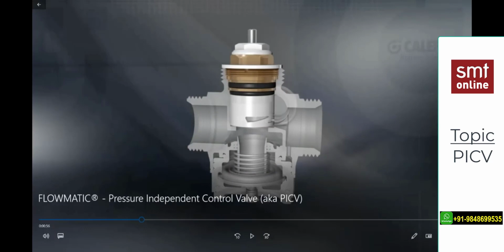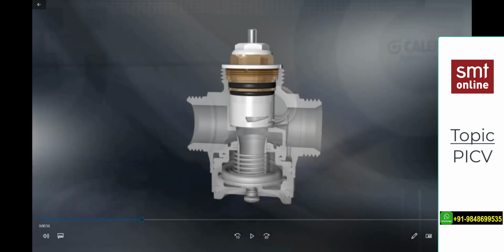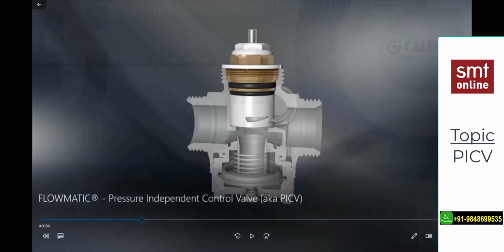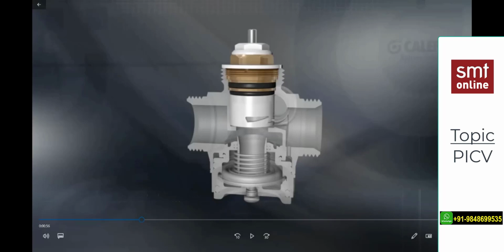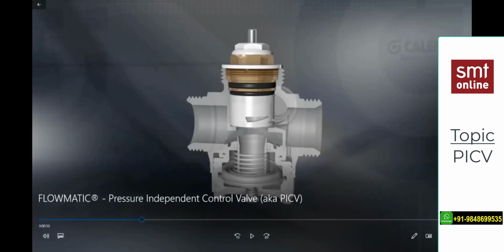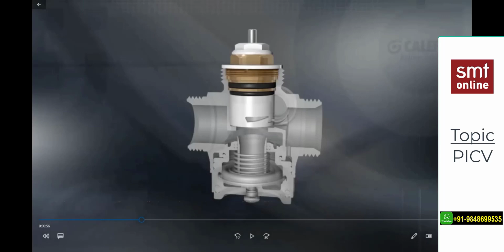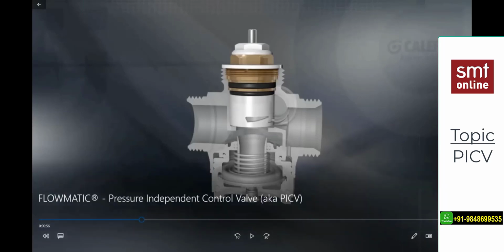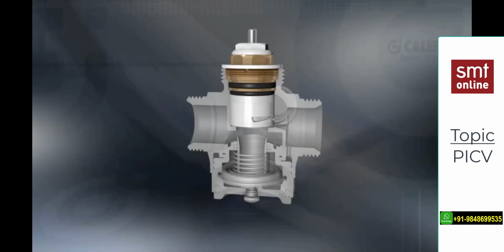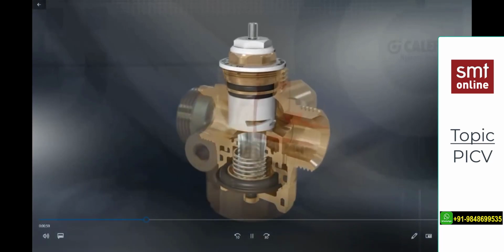And you see, just now, the rotation is for adjustment. The first time, we are going to adjust this to the required percentage, and I'll show you how with the table. When you rotate, this opening is for the initial adjustment, and with that we will lock it. Then the shaft will automatically push up and down with the actuator as per the temperature requirement in the space. This is for balancing.